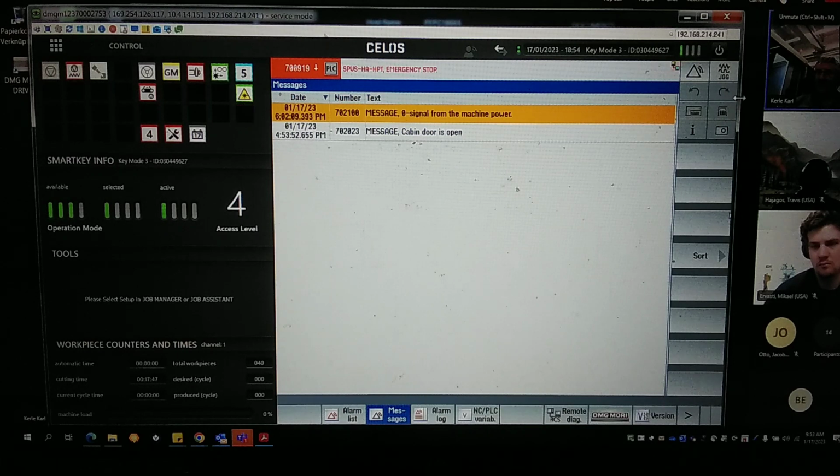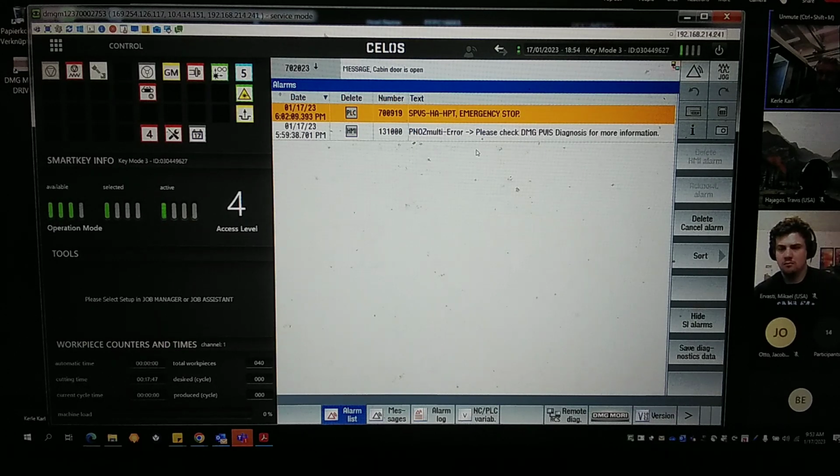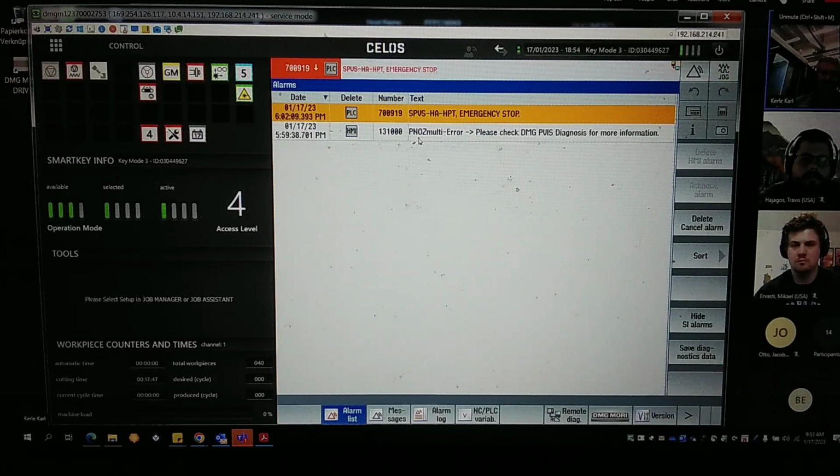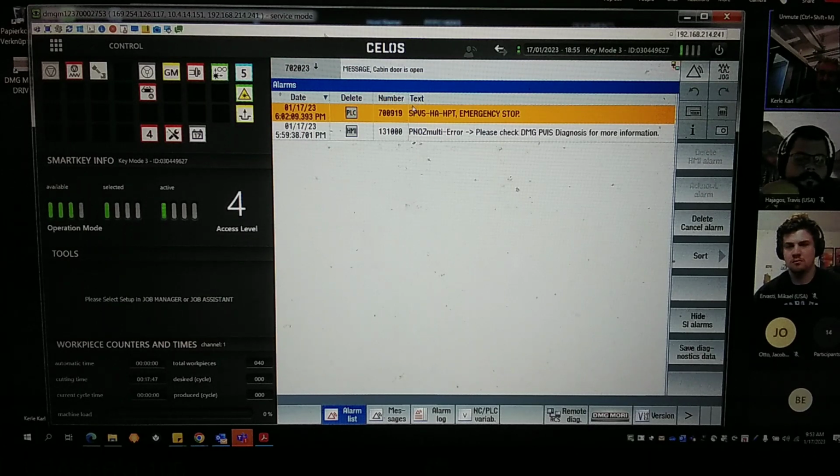And for example, in diagnostic, we also have here the alarms indicated like emergency stop, and also here you see PNOZmulti. You know what it means, that PNOZmulti? When you remember, I have shown you, these are the yellow-green boxes in the middle height of the rear side wall of the control cabinet arranged, yeah? Okay? These are the so-called monitoring or safety boxes. They are specially designed to check primary and secondary emergency stop chains. Okay? So far so good?